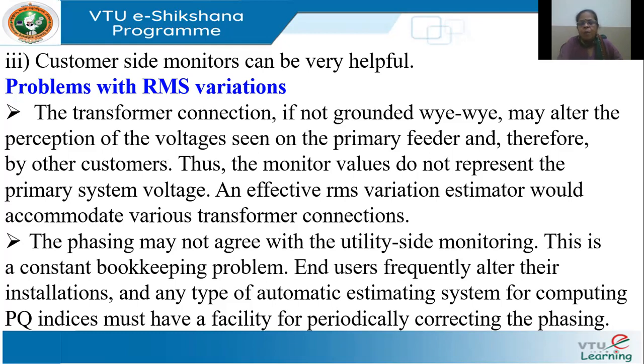And another problem is what is called the phasing problem. That means the utility would have installed meters in, say, R, Y, B phases, presuming some load is connected to R, some to Y and some to B. Now, on the customer side, they may interchange the loads. That means they may change the phases. For example, take an industry. I have R, Y, B. The industry has connected all their lighting load in phase B.